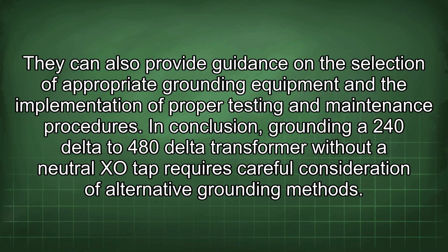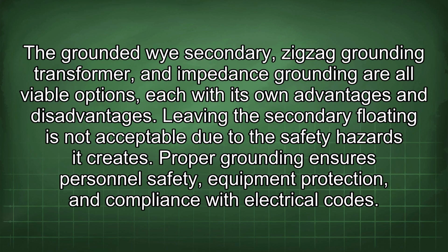In conclusion, grounding a 240 delta to 480 delta transformer without a neutral XO tap requires careful consideration of alternative grounding methods. The grounded Y secondary, zigzag grounding transformer, and impedance grounding are all viable options, each with its own advantages and disadvantages. Leaving the secondary floating is not acceptable due to the safety hazards it creates.